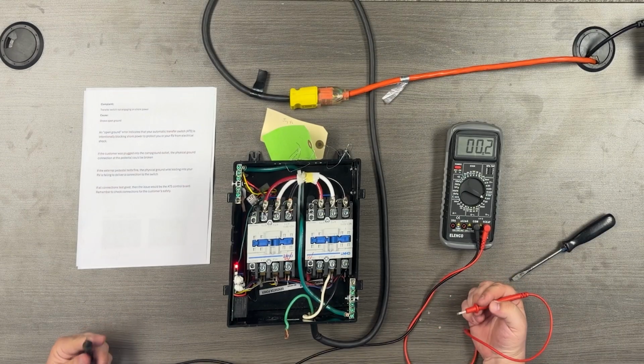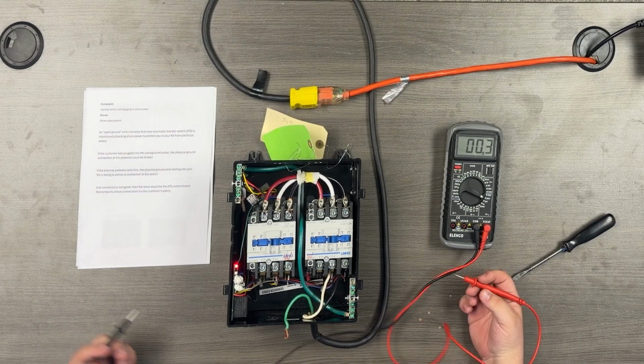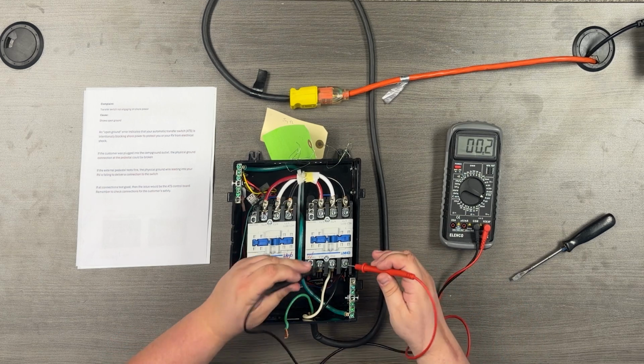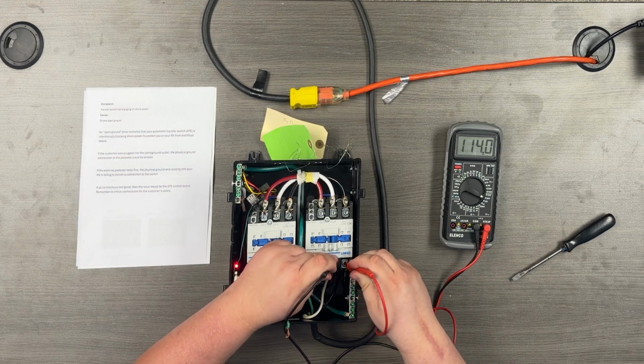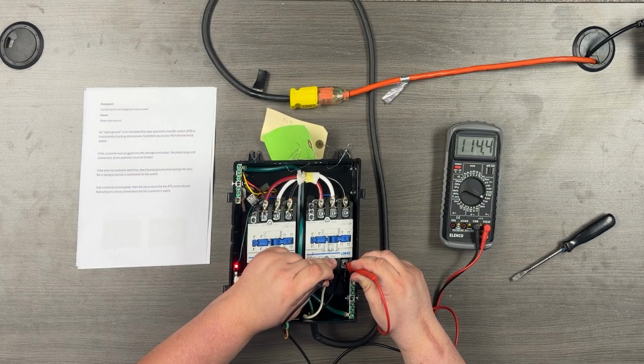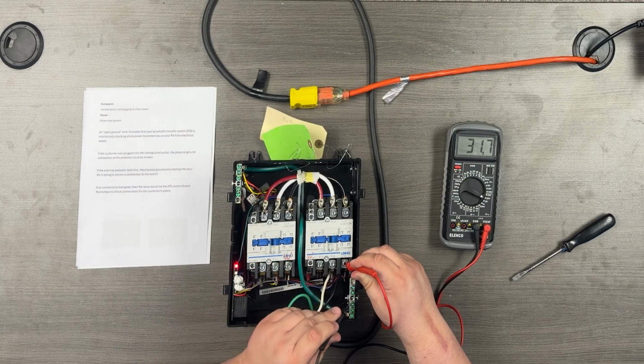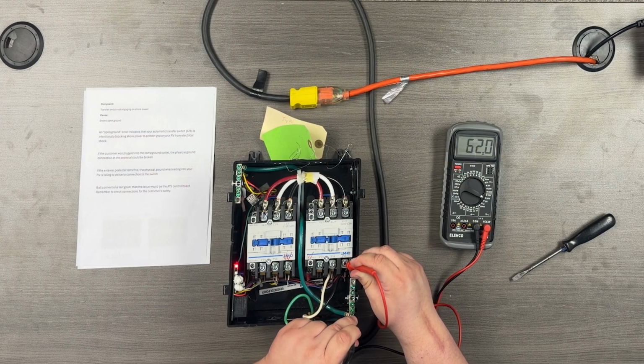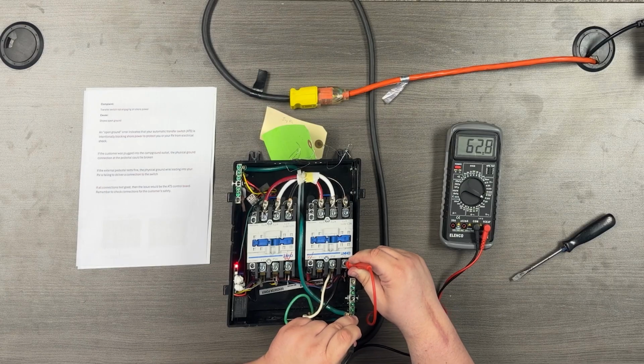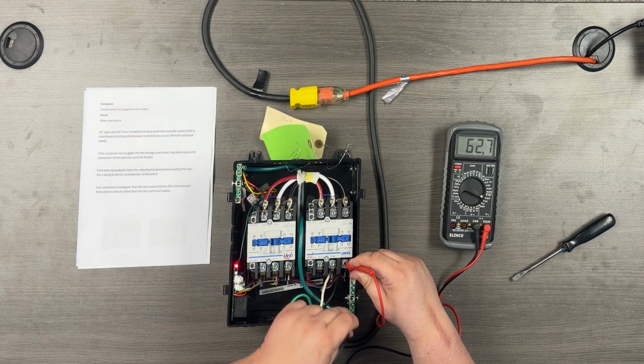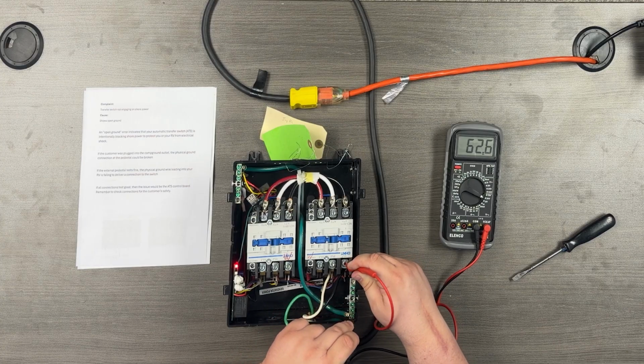So the way that you would test for an open ground with your multimeter is that you're going to take a test and look at your voltage here. From hot to neutral, I see about 114 volts. But if I test from hot to ground, I see significantly less voltage. This is indicating to me that I have an open ground here. I've got some voltage floating over to my ground, and that's what we don't want.